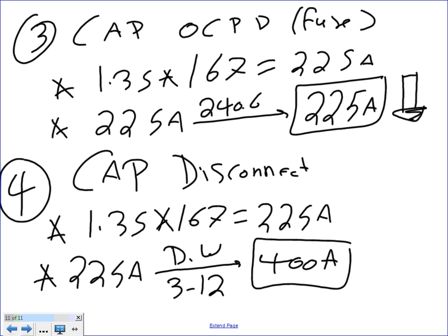So this is typically what you're going to be sizing most of the time. When I worked for Elliott Hendrickson, we had a 15 horsepower motor. When we size it, right next to it, we size a capacitor that goes with it. A lot of motor manufacturers will help you with this calculation. You do them so you can look intelligent before you go talk to a vendor. You do your calculation, then talk to the vendors, and tell them, here's my calculation. If they say that's what they specify with their equipment, good to go. You sound a little more knowledgeable before you talk to the vendors.